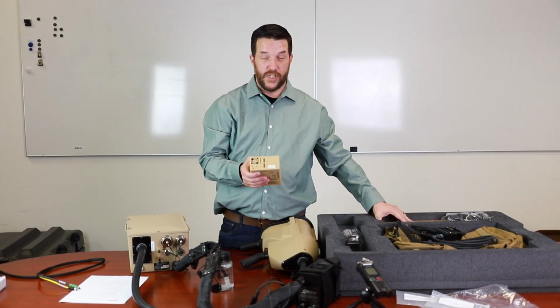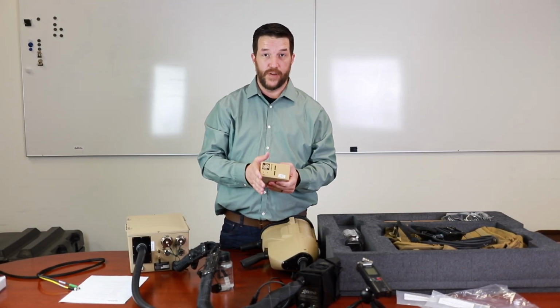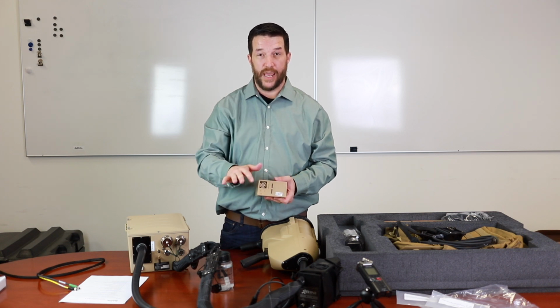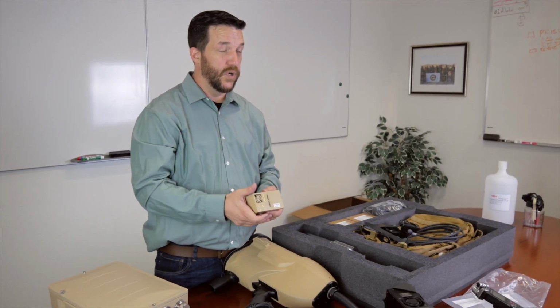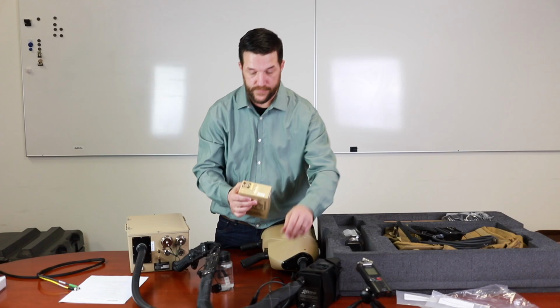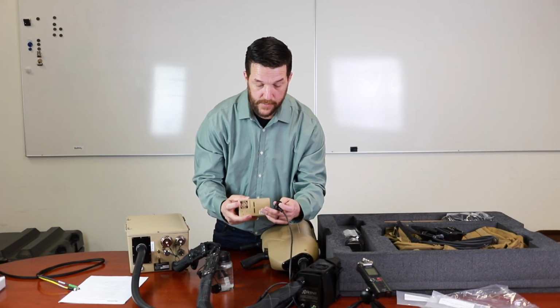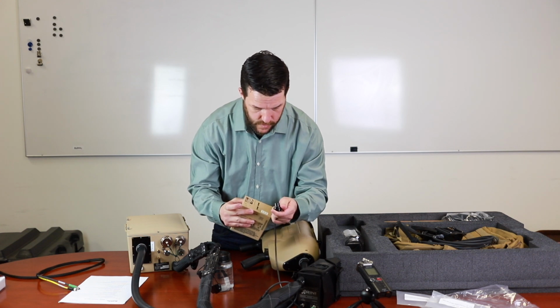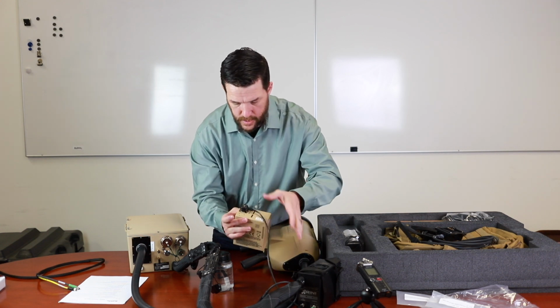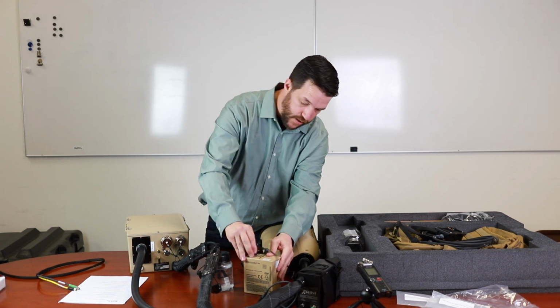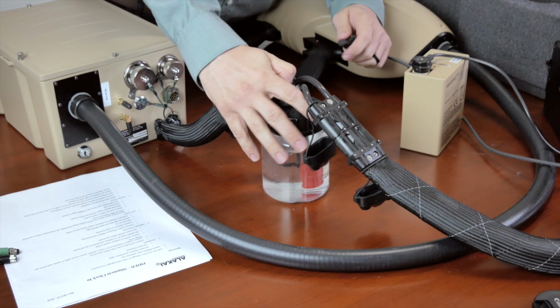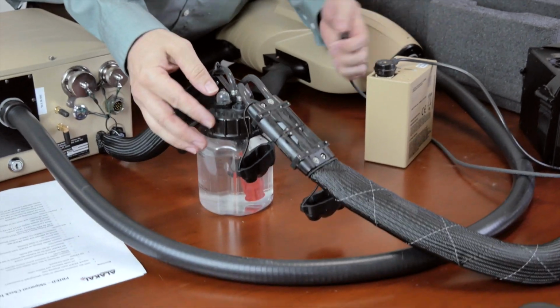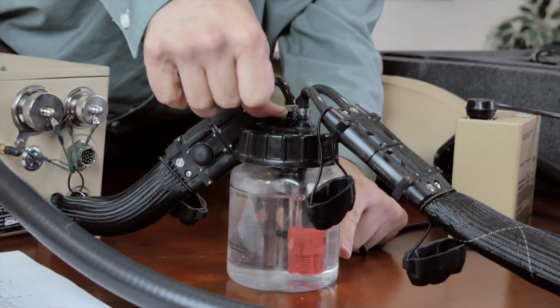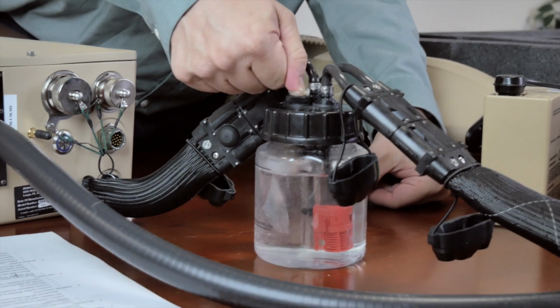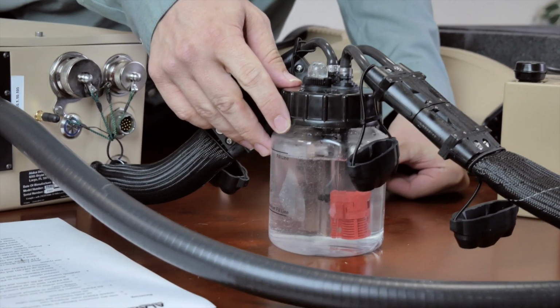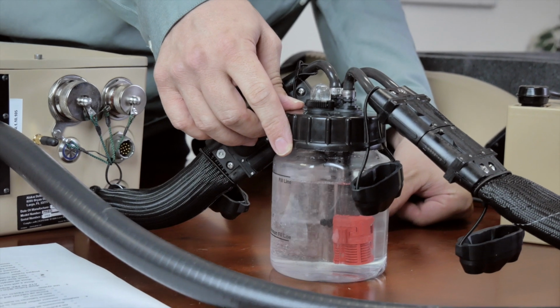On checking in of your system, the batteries come about 30% filled. So you should be able to knock out a fill using your batteries, but they will need a full charge upon arrival. The batteries themselves and the control cable are also keyed, so make sure you find the correct location. And then it will sit in very, very snugly. There we go.